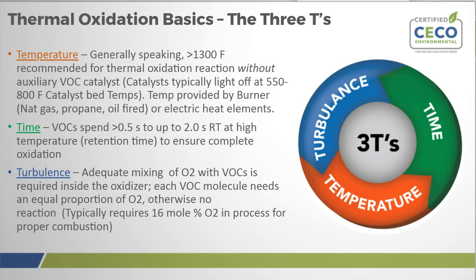Catalyst units typically will light off or activate at 550 degrees Fahrenheit to about 800 degrees Fahrenheit. So catalyst is not applicable for all applications and all VOCs. You typically want to stay away from heavy metals, silicone-laden compounds, and acids, and heavy metals like lead, antimony, and those types of things. But catalysts can provide some energy efficiency because they use a lower temperature to activate on the catalyst. And the purification reaction there is not in a retention chamber, but over the catalyst. We'll talk about that later.